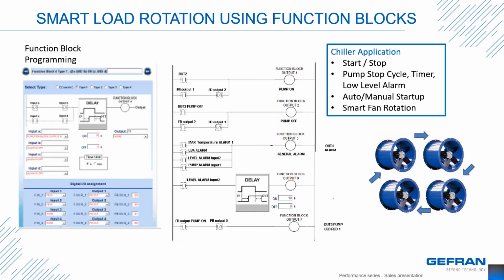In this chiller application, we needed specific functions like start-stop, pump control, timer, auto manual. In this application, we have 4 fans for cooling. So rather than always starting fan 1 to cool, we rotate which fans are used, so we wear them out equally. In the past, to do an application like this, you needed a logic card, a timer, a temperature controller. Now you can merge them all together.